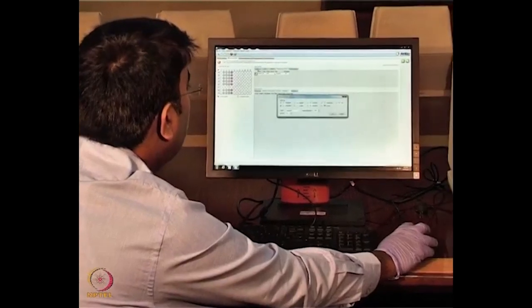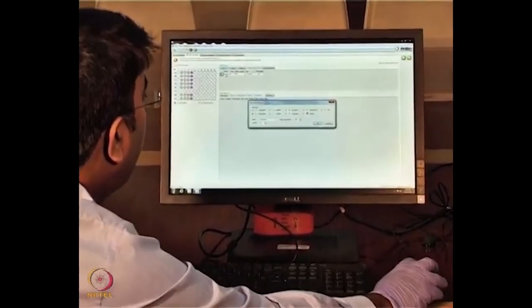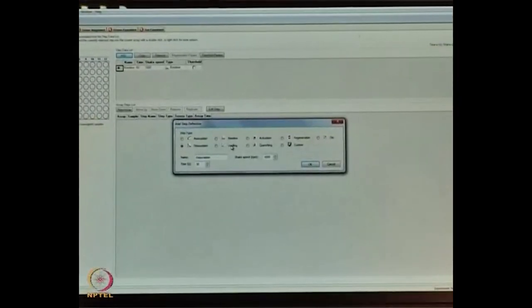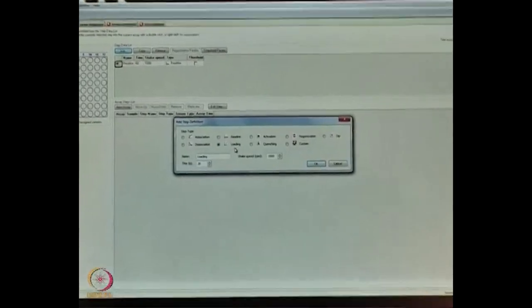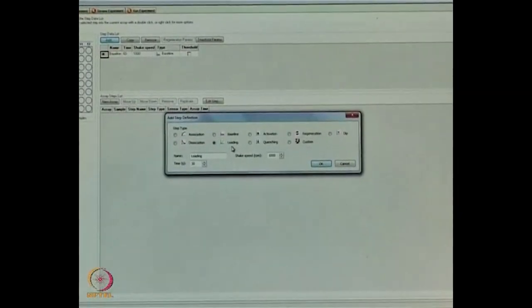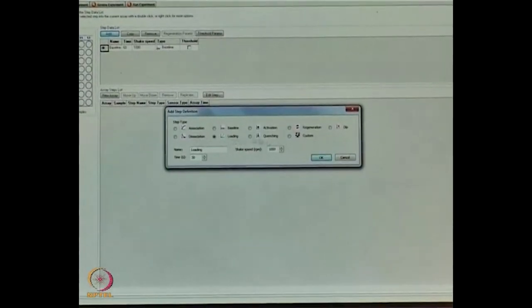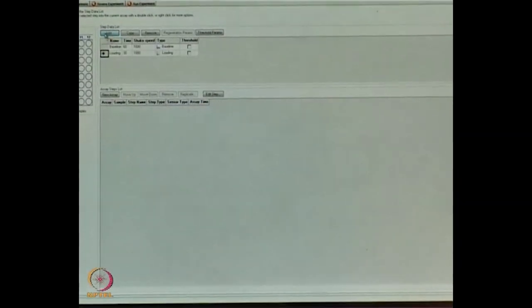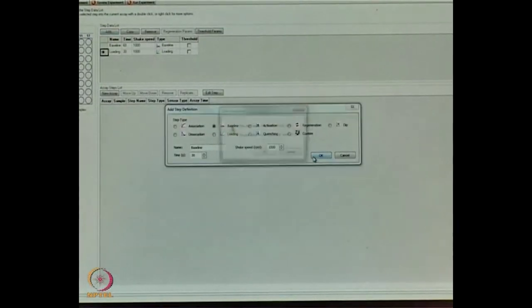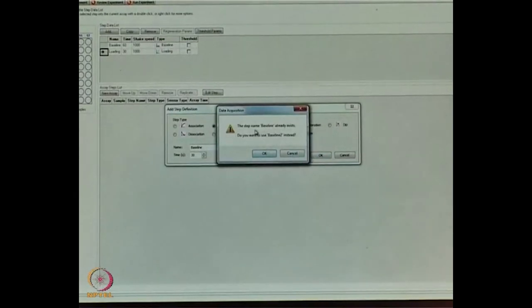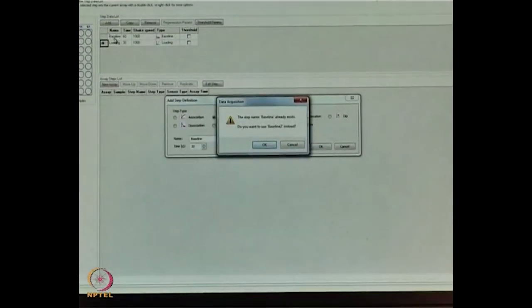Now there is one more step, which we call assay definition. These are the steps I am going to add here. There is a baseline by default, which just acquires the buffer. The next step we call loading. Loading is nothing but immobilizing 10 micrograms per ml protein A onto the streptavidin sensor. I am going to add that, then the next step I perform the baseline and say OK.